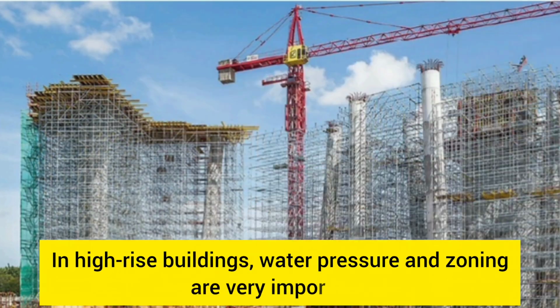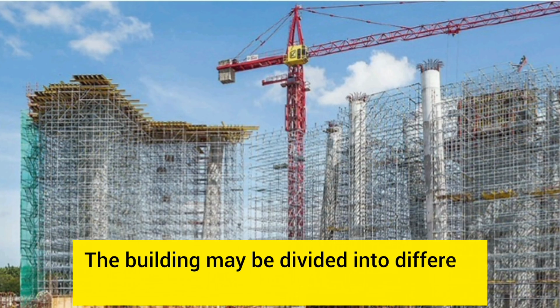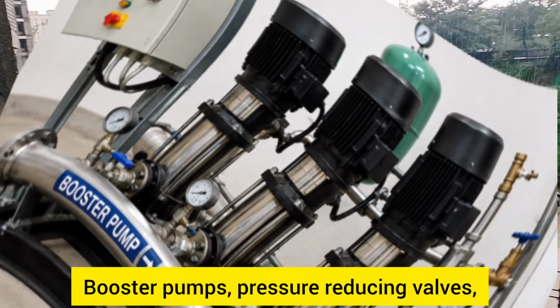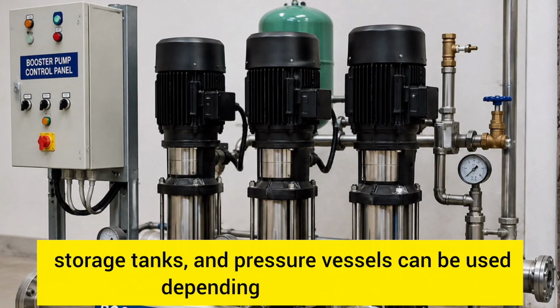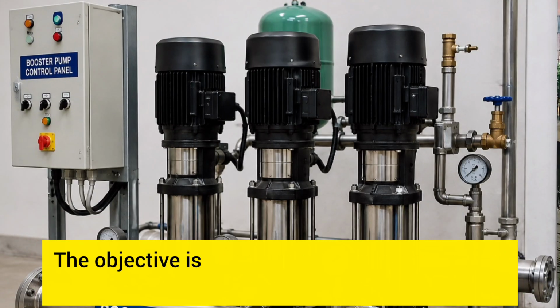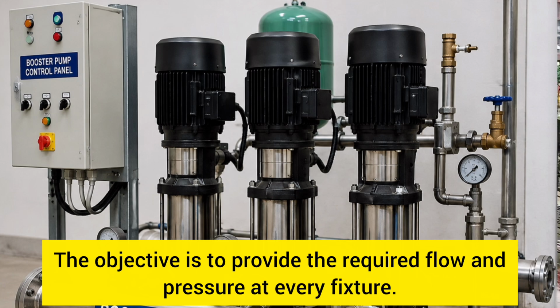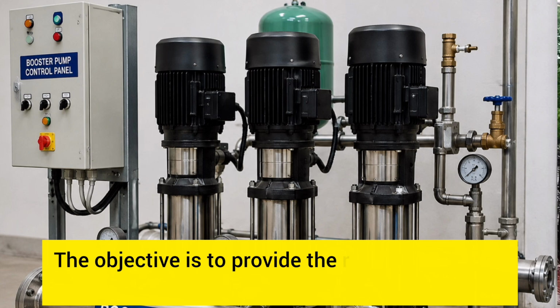Water supply in high-rise buildings. In high-rise buildings, water pressure and zoning are very important. The building may be divided into different pressure zones. Booster pumps, pressure-reducing valves, storage tanks, and pressure vessels can be used depending on the design. The objective is to provide the required flow and pressure at every fixture.